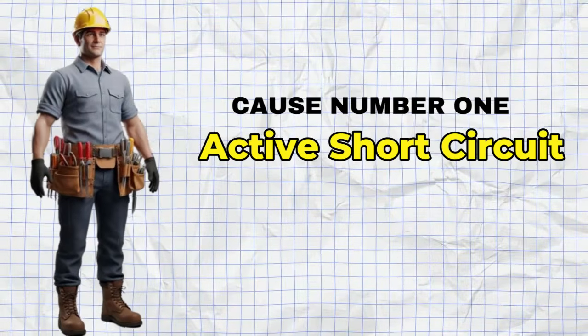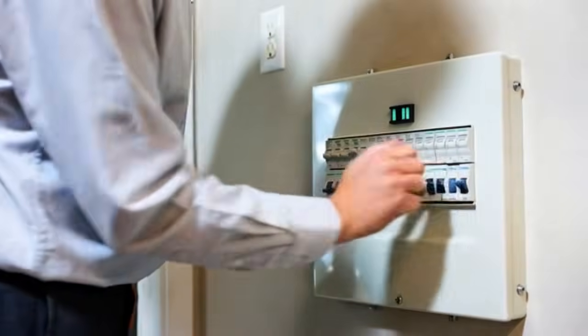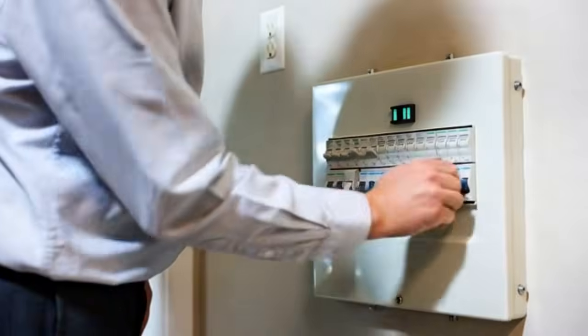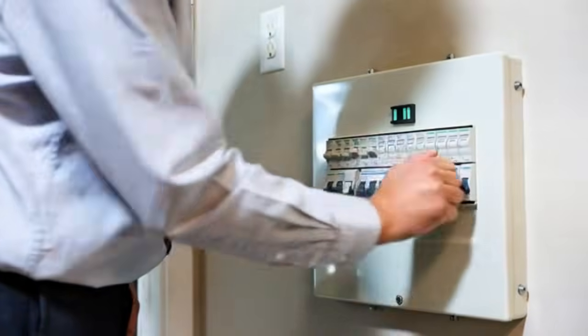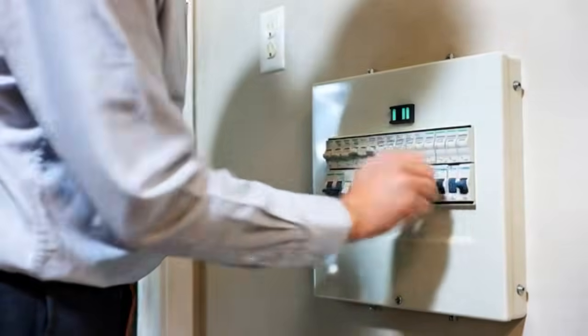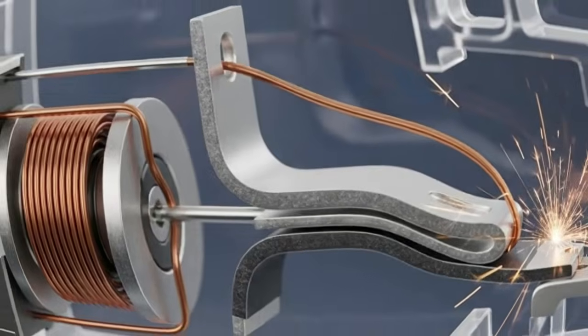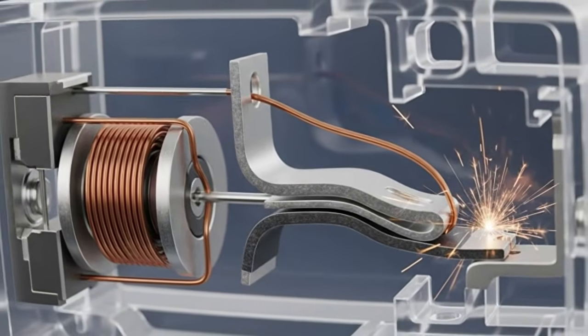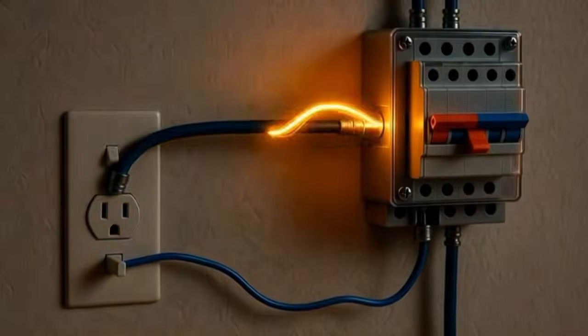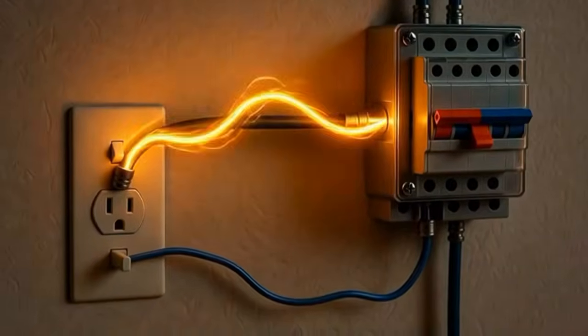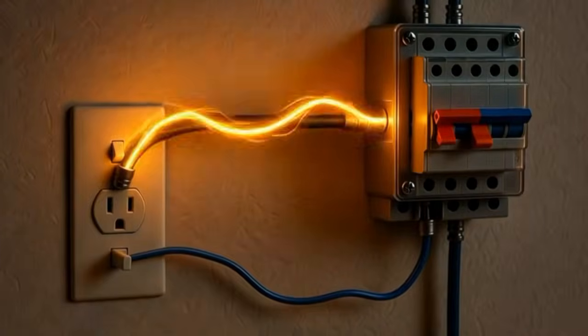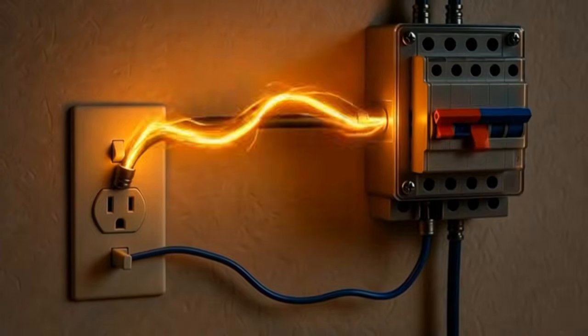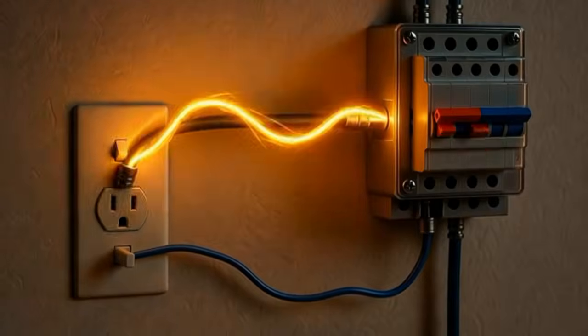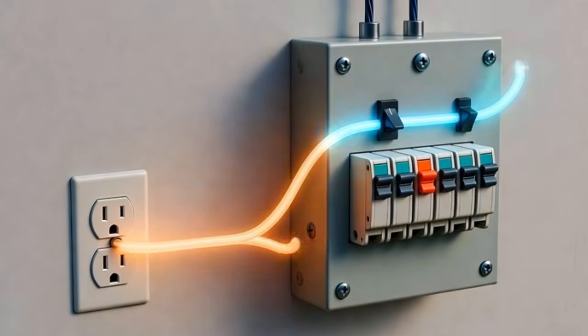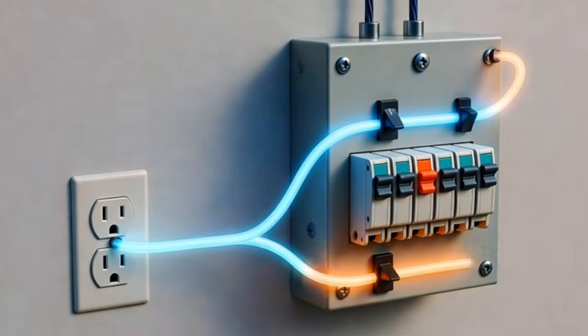A short circuit is the most common reason a breaker refuses to reset. A short circuit occurs when a hot wire makes direct contact with a neutral wire or another hot wire. This contact bypasses all the normal resistance in the circuit, the lights, outlets, and appliances that would normally limit current flow. Instead, electricity rushes through the low-resistance shortcut with almost nothing to slow it down. The result is a massive current surge. We're talking hundreds of amps flowing through wires rated for 15 or 20 amps.